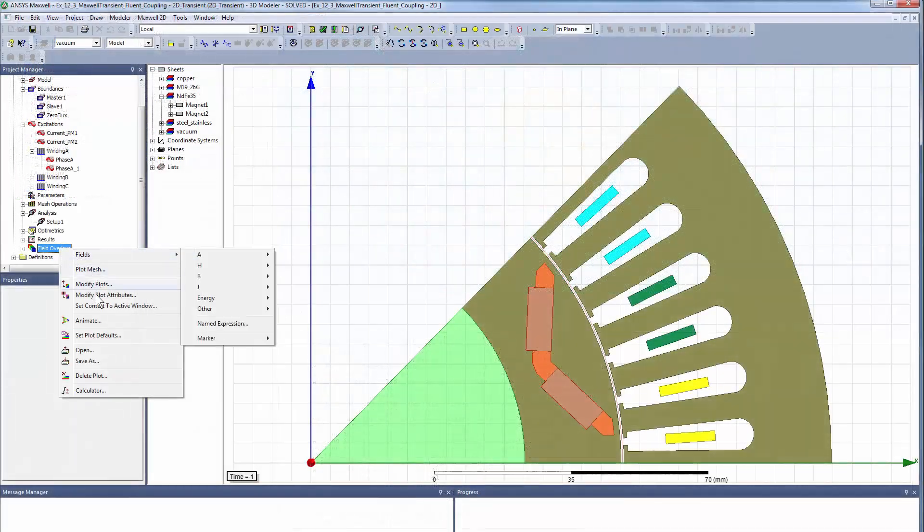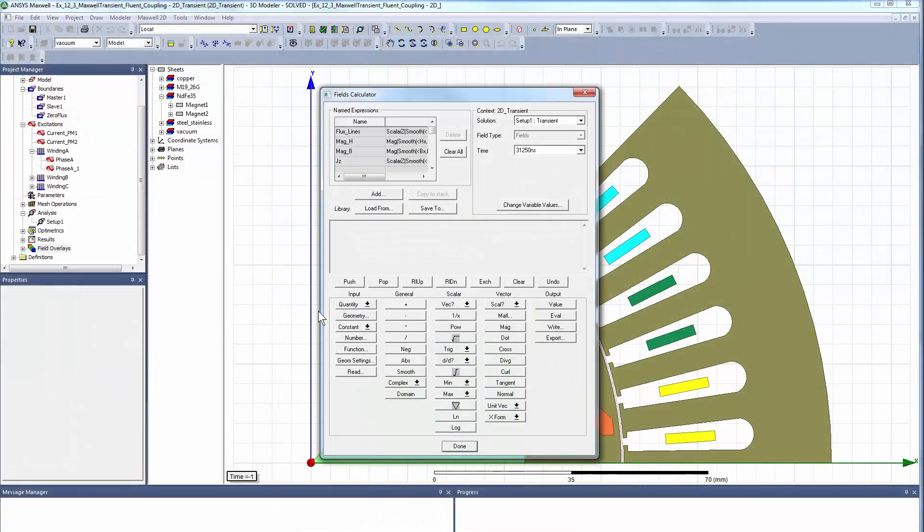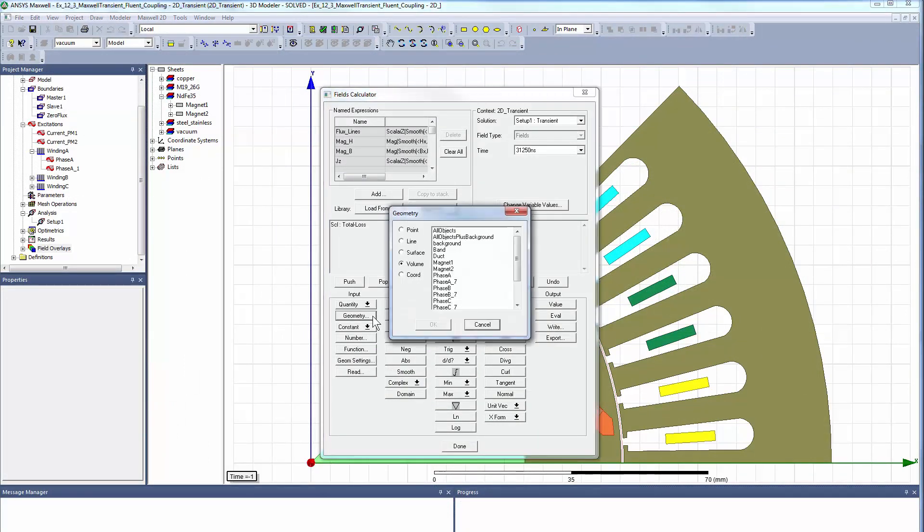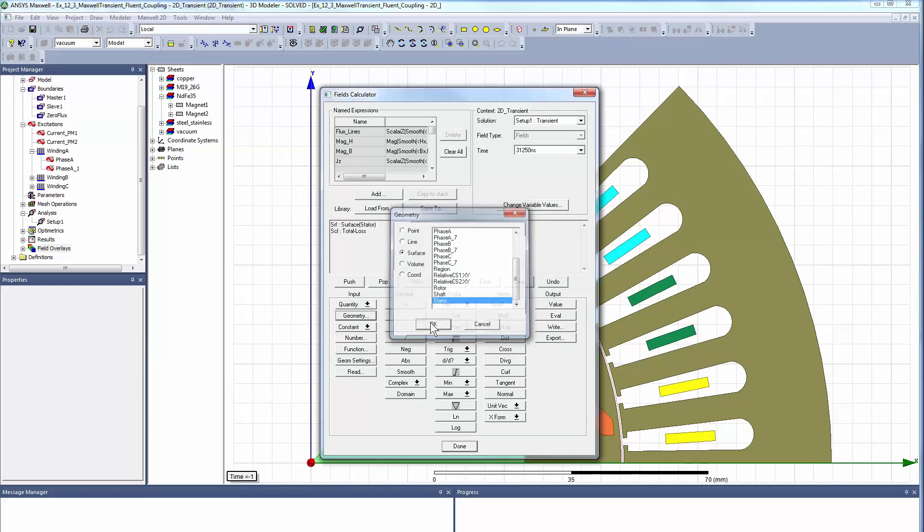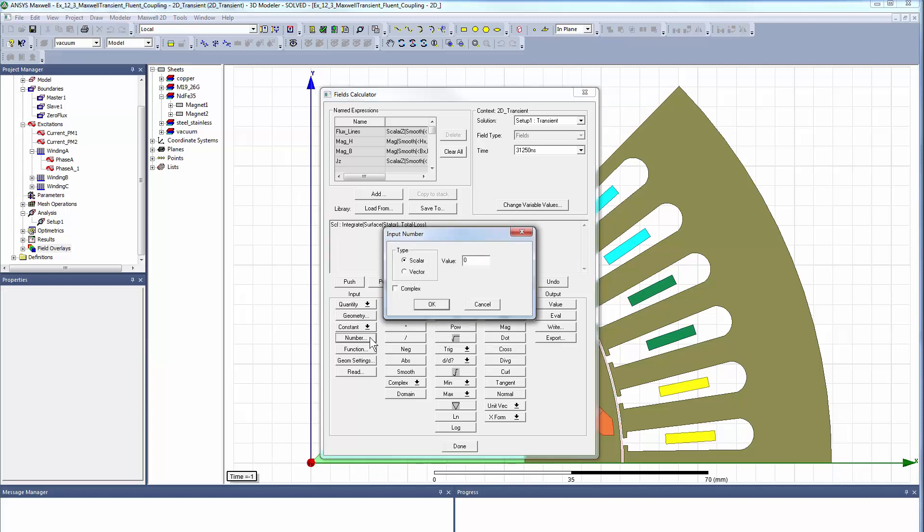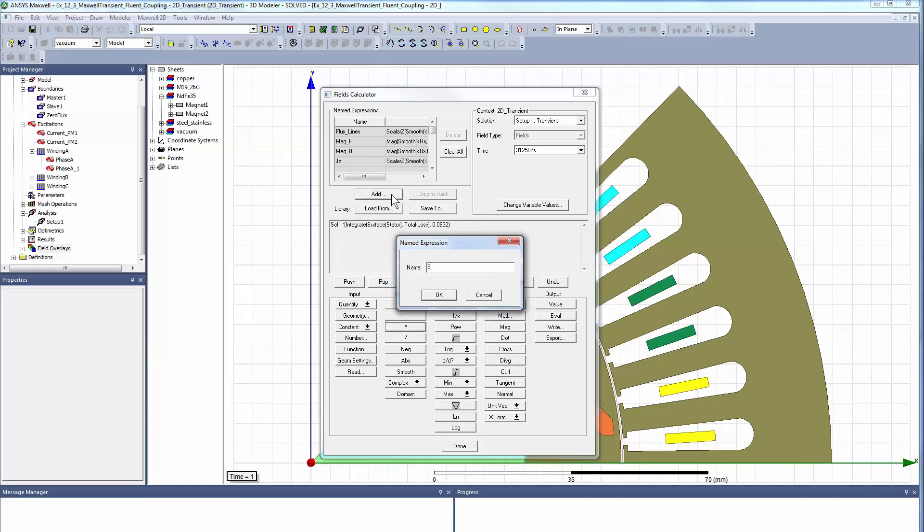Maxwell 2D simulation is very fast and is now complete. We now exploit Maxwell's post-processing capabilities by using the field calculator to compute the losses and further validate the accuracy of the loss mapping into 3D CFD. To do this, we calculate the generated stator loss. We input a scalar for the axial length here. This defined expression becomes available for the overall post-processor.